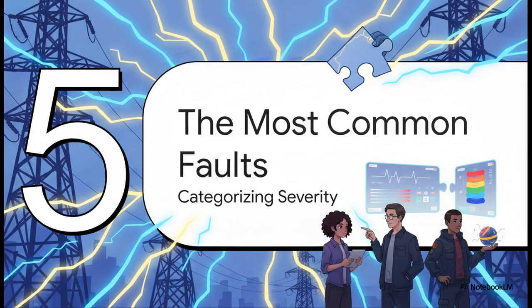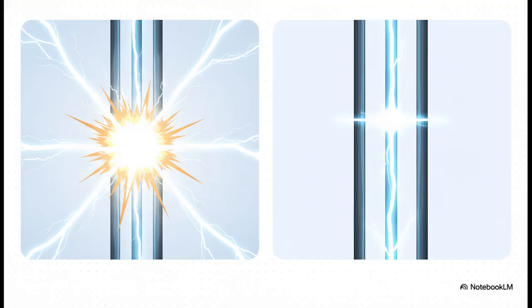And finally, Section 5, the most common faults, categorizing severity. Here is where it gets really interesting, because engineers categorize these short circuits into two specific types based on symmetry. First, symmetrical faults. These are thankfully super rare, only about 2 to 5% of all faults, but they are absolute grid destroyers. The system technically stays balanced, but the sheer volume of current across all three phases will just obliterate the equipment. Then you have unsymmetrical faults. These are incredibly common, generally far less severe, and they unbalance the system because each phase ends up with a different impedance. They are basically the everyday nuisance that grid engineers are constantly managing.